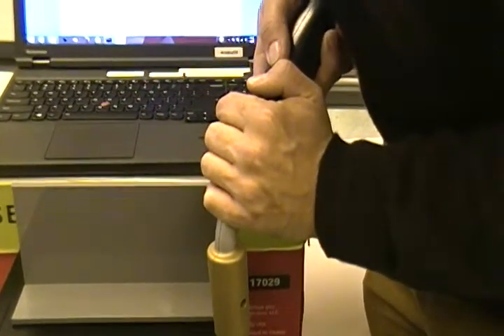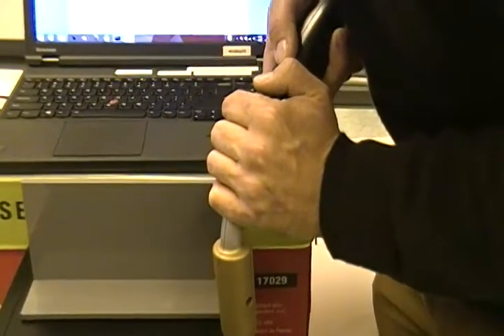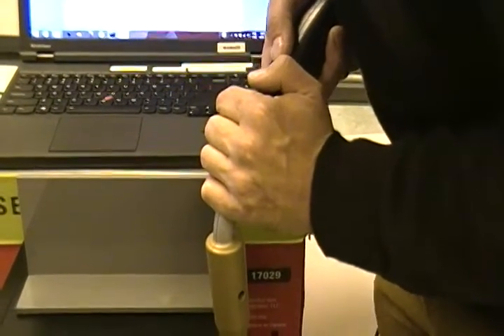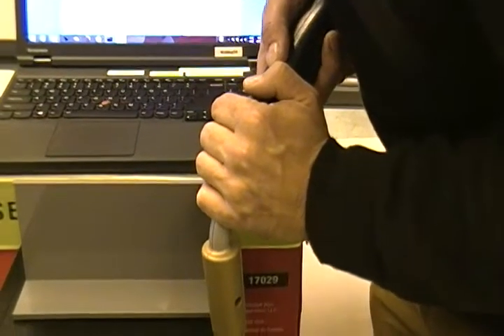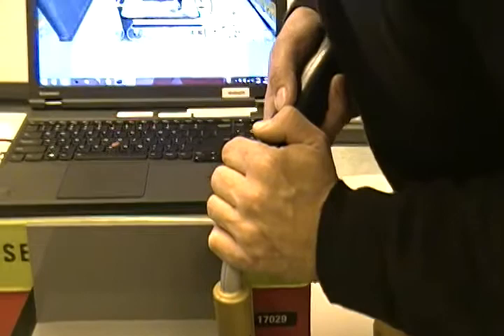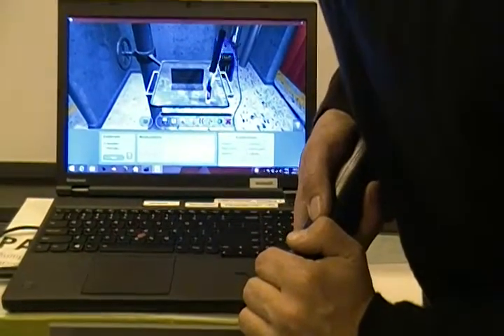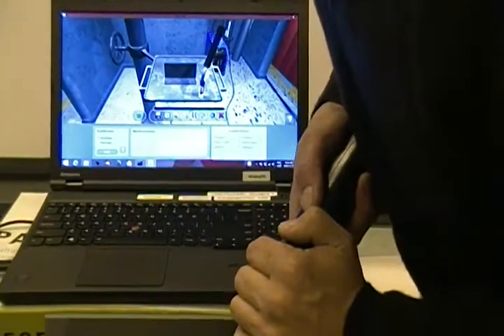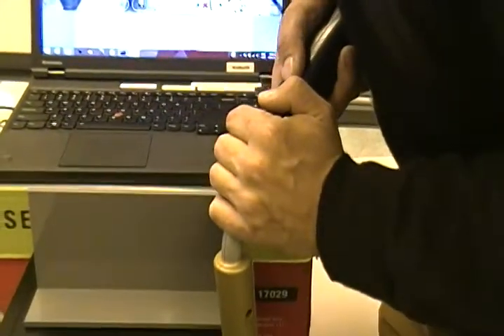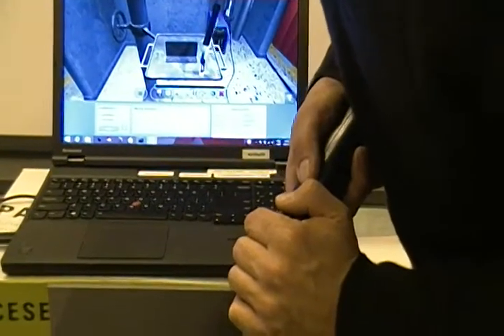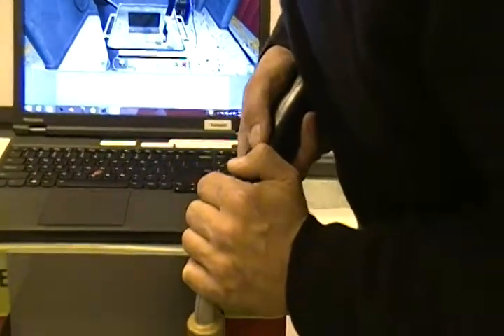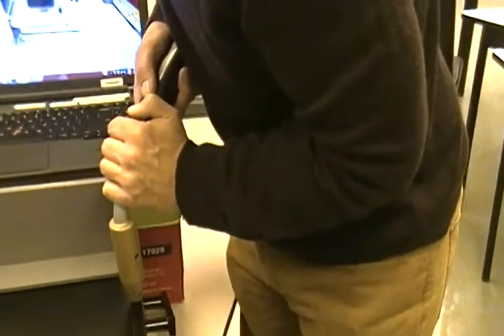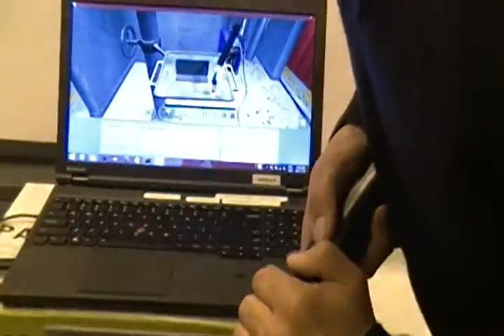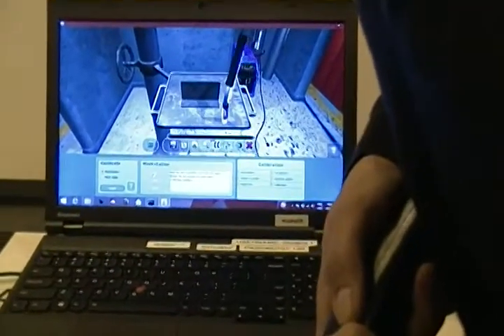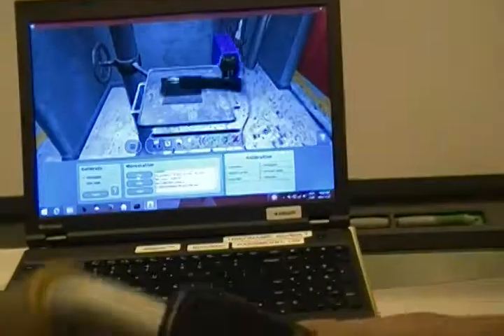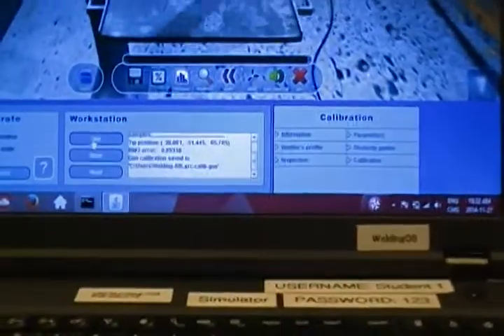And this is a little bit tricky. Make sure that this is on a stable ground. I just noticed this table is a little bit uneven. But as I go back and forth, it's collecting the sample. Now with this sample, you want it to be under 1. I've had it under 0.4, but sometimes I'm at 0.8. But you have to be under 1. And you'll see right here, the data will come up, and I'm just keeping my elbows real tight close into my body to keep it steady. It's almost done here, and I am at 0.89, which isn't great, but for our calibration purposes that will work.